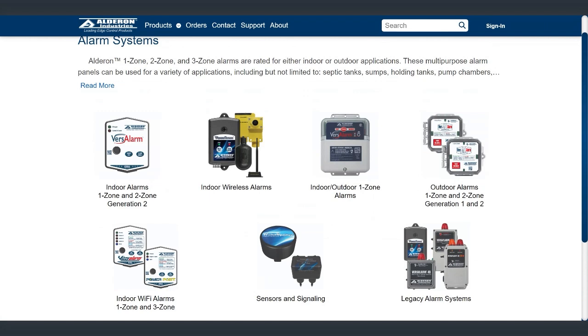With ours, you can do a mesh network as well for the panels or the alarms. And you can actually hook up 8 of these in series, so you can have one panel 1,000 feet away from your hub, and then another panel 1,000 feet away from the second panel, another panel 1,000 feet away. So you can be like 8,000 feet away and still get data connectivity. And with all of those, you can get pump run, you can get amp draw, you can get elapsed time, event counts, high level alarm, low level alarm indications.